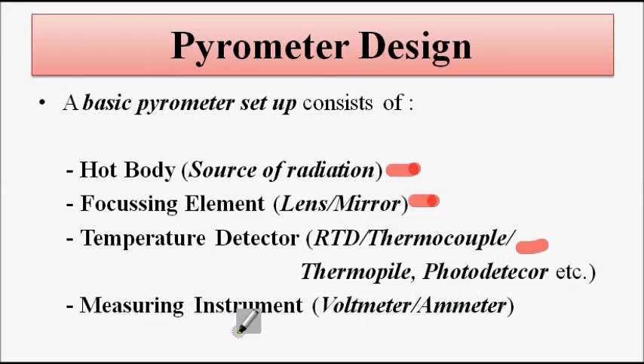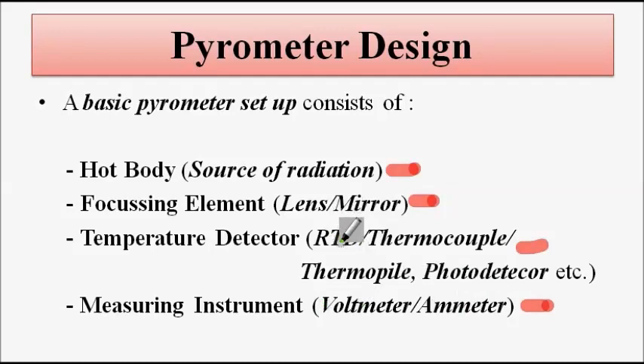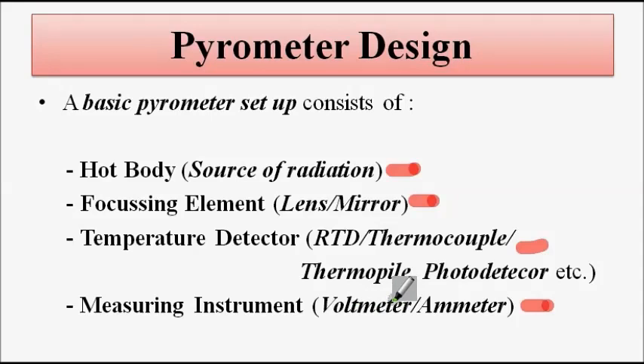Next is a measuring instrument so that we can get the output in terms of voltage or current — a voltmeter or ammeter. RTD gives output in the form of resistance change, so we can connect it to a voltage divider or Wheatstone bridge setup to convert it into voltage or current, which can then be measured with a voltmeter or ammeter. Thermocouples and thermopiles give output directly in terms of voltage, so in that case we only need a voltmeter. Depending on what type of transducer is used, the signal conditioning circuitry may vary.